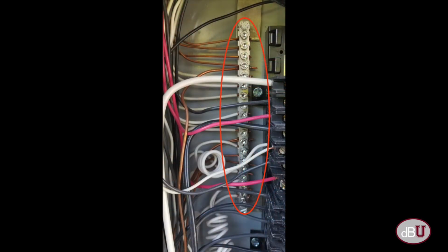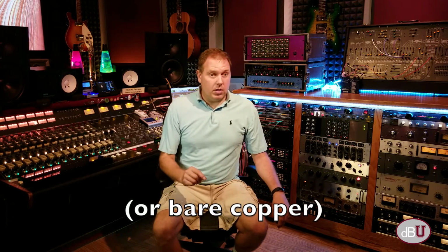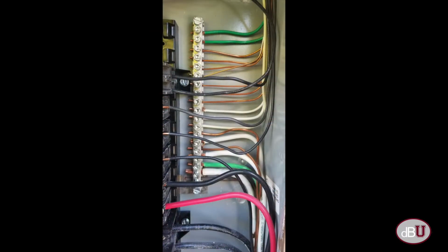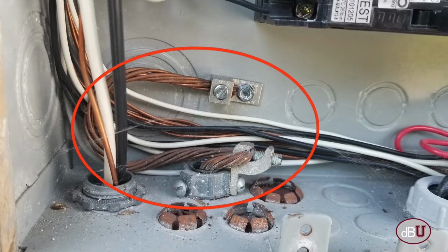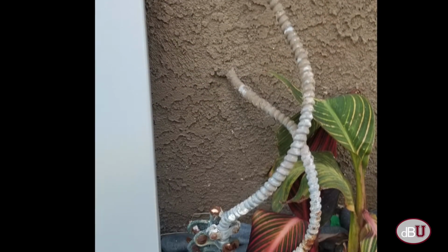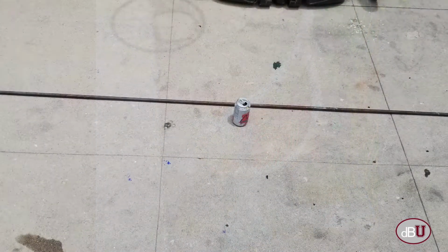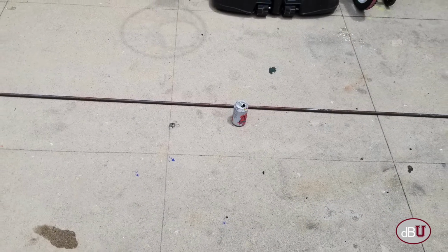This white wire is terminated in what's called a busbar. It's really just a metal block with a bunch of screws in it. That bar is fastened to the inside of the electrical box. The third wire is green, which is the ground. All of the green wires connect to another busbar, which is also fastened to the inside of the box. This bar further connects to a large copper wire, which leaves the panel and is ultimately fastened to a copper rod that is pounded deep into the ground, outside the box.